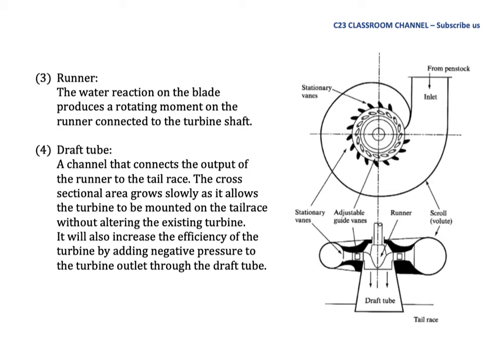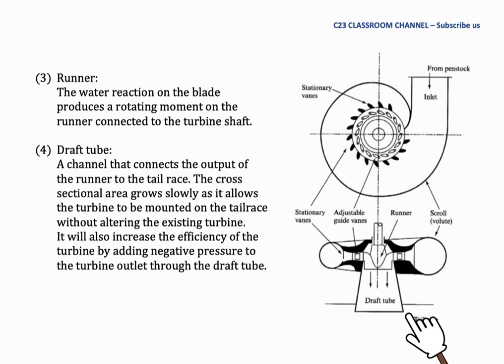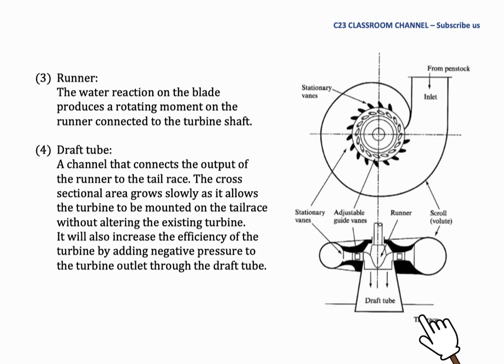Number four: Draft Tube. A channel that connects the output of the runner to the tailrace. The cross-sectional area grows slowly as it allows the turbine to be mounted on the tailrace without altering the existing turbine. It will also increase the efficiency of the turbine by adding negative pressure to the turbine outlet through the draft tube. It is normally designed bigger at the end to make sure that water will flow out easily.